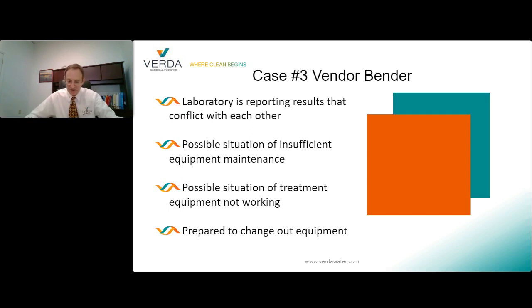So at this particular hospital, the local laboratory performed the conductivity and the hardness test and reported that the critical final rinse water conductivity was 2 microsiemens per cm, and the water hardness was 30 milligrams per liter. So the first number was great, right? 2 microsiemens per centimeter.